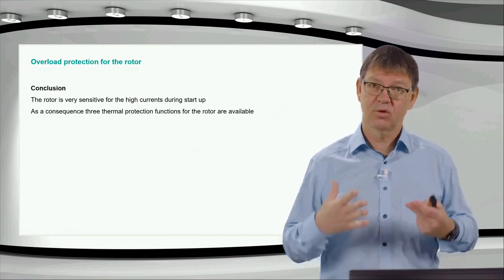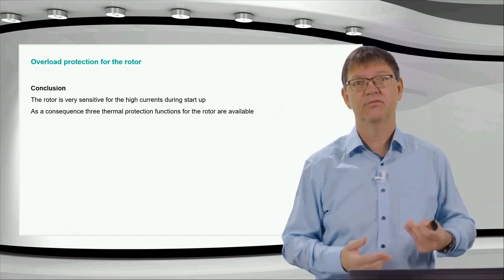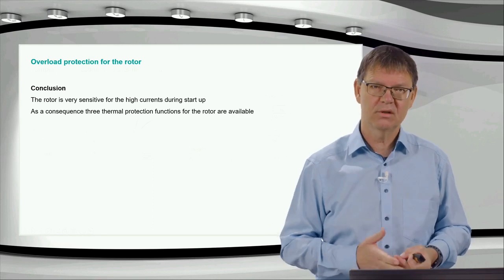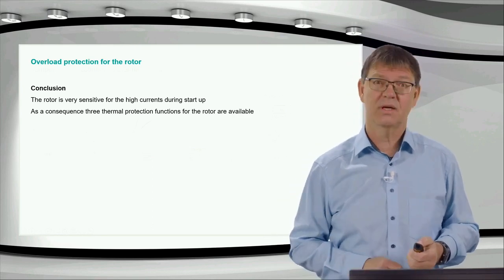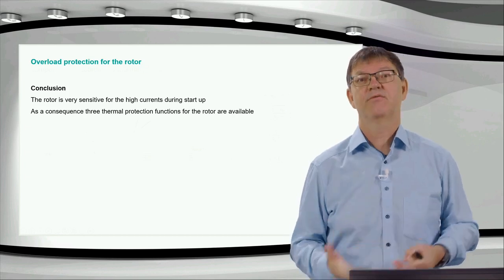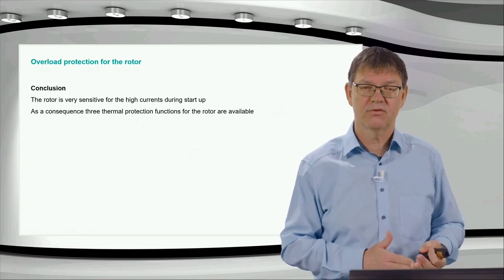Okay, what comes next? Conclusion. The rotor is very sensitive to the high currents during startup. I have normally a relatively small time constant according to this model. So the temperature goes up very much faster than with a stator. And as a consequence, because we have different situations as well, we have various protection functions here.